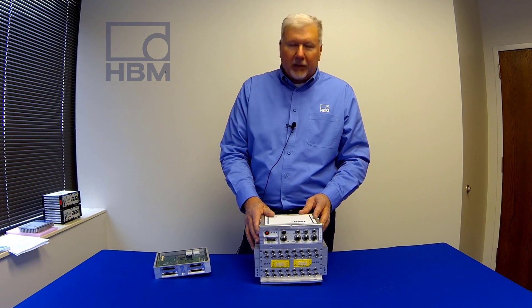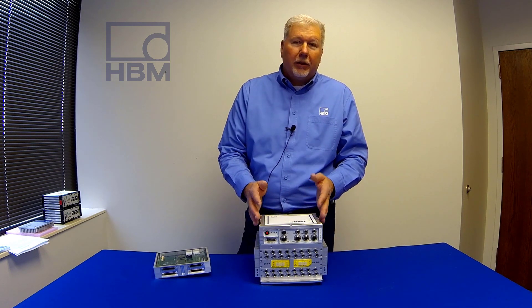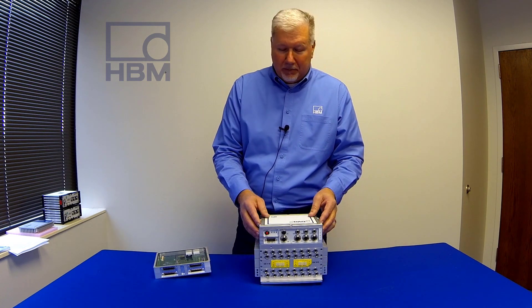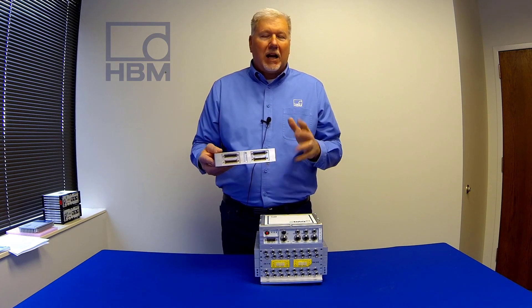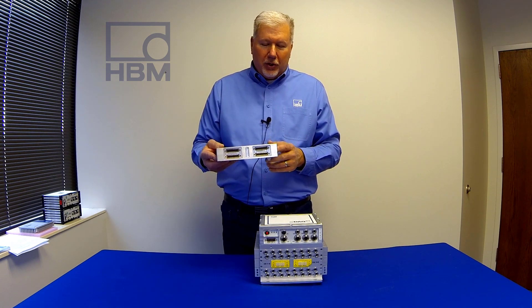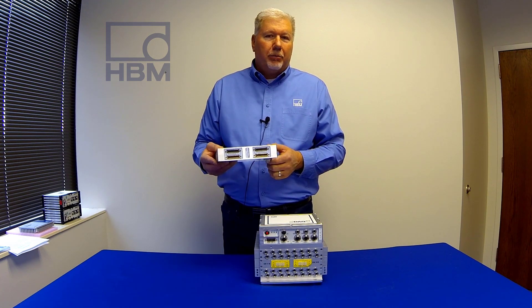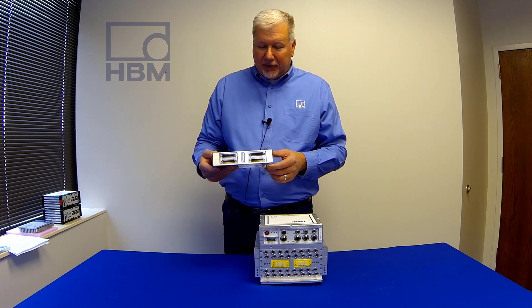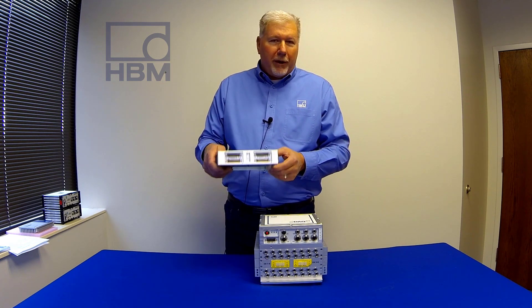In the future, we'll be developing new signal conditioning layers for the eDAQ XR, which will allow you to build the system up as well as utilize your legacy layers at the same time. For example, we have what we're calling the bridge board — it's actually a combination of an HLS and a bridge board, for those who know the products from the eDAQ family. This can do a wide range of analog inputs, up to 200 kilohertz samples per channel, sense lines, quarter, half, and full bridge, 120 and 350 ohm. More information will come on this.